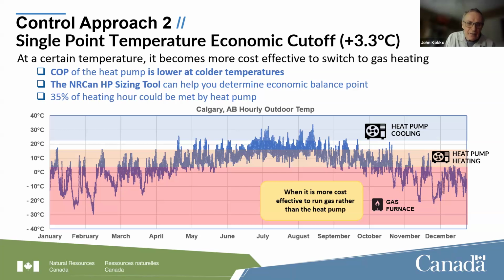And for this particular example, that turns out to be about 3.3 degrees C, plus 3.3. So if we're going to use that economic cutoff point, it says we're going to bring the heat pump on when our heating season starts, and we're going to let the heat pump run down to about plus 3.3 degrees C outdoors. Below that, we're going to run gas heating, and again, when the temperature rises to about 3.3, then we turn on the heat pump to run above that temperature.